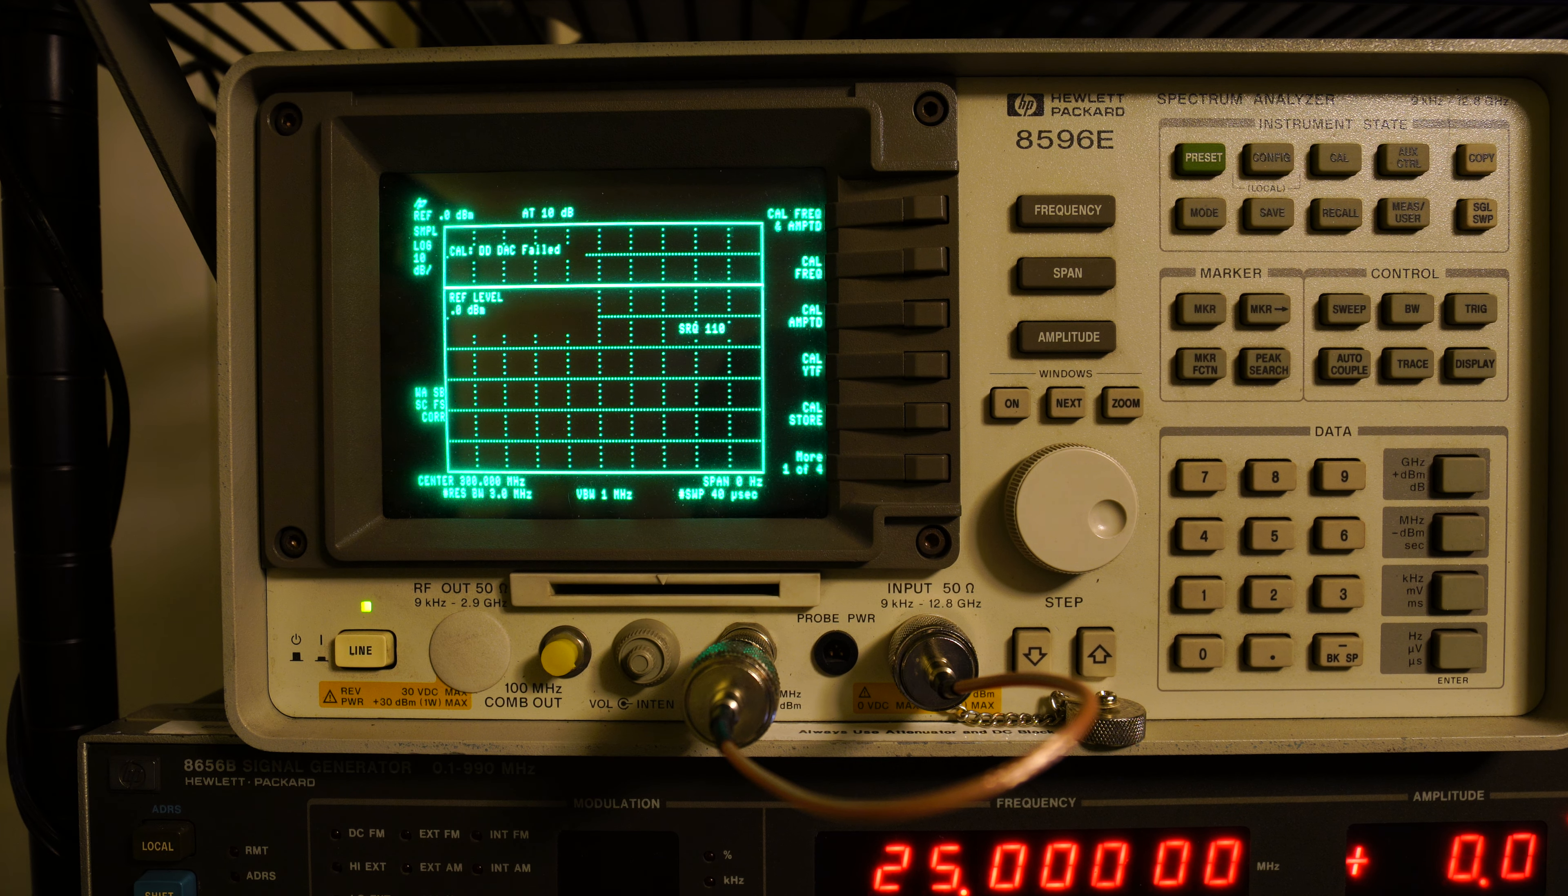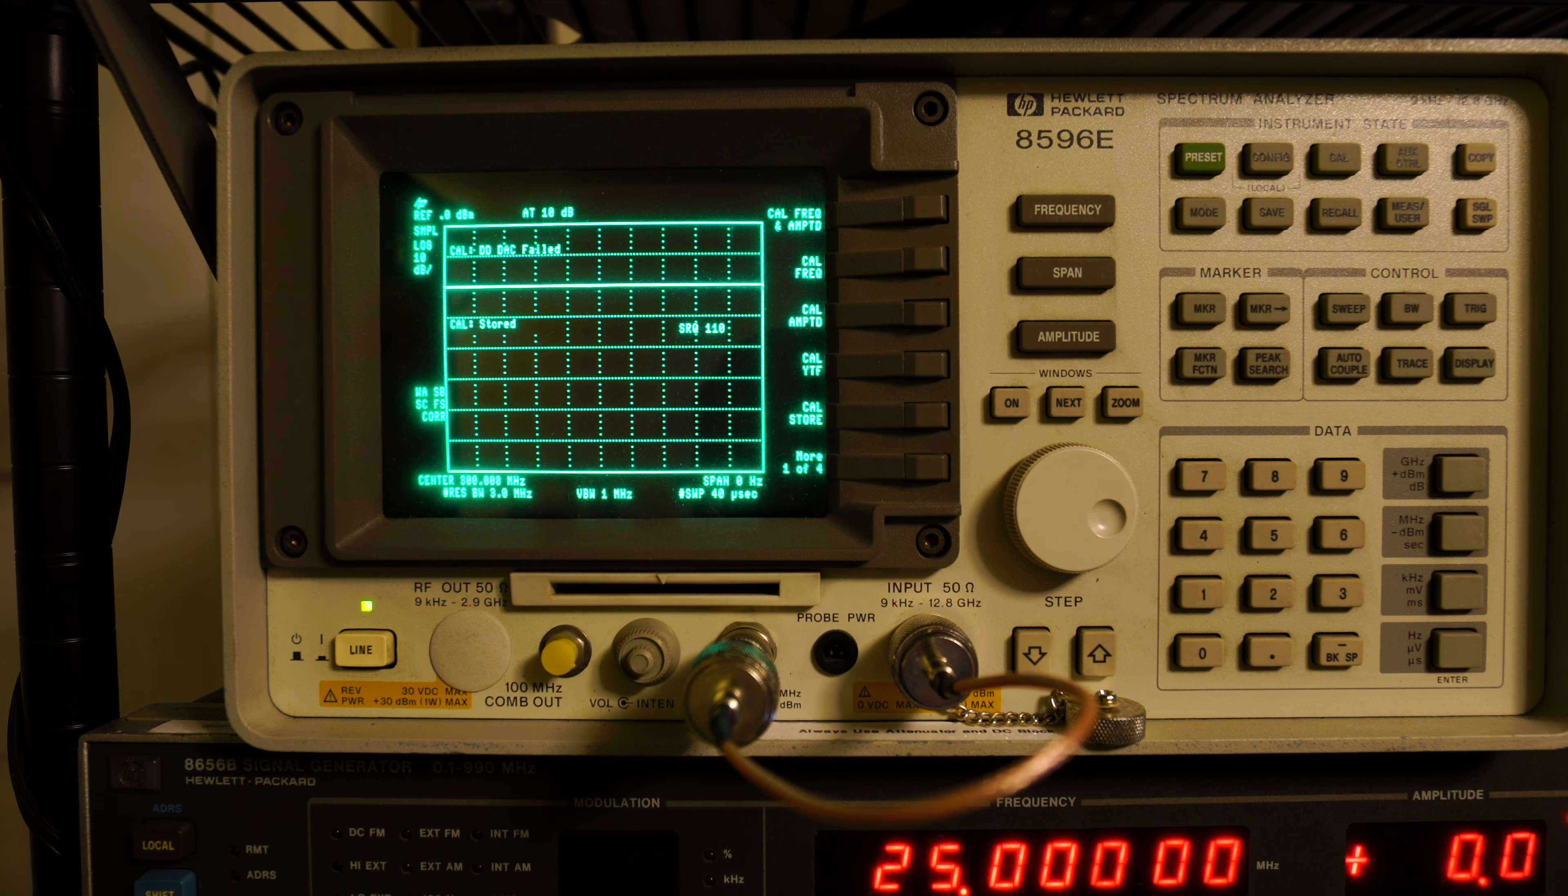All right, there it is. It's finally finished and all you've got to do right here - it says Cal Store. See that? I hope you can read that. Press that and it says Cal Stored. It's through, it works. And then if I press Reset, it'll come back with just that display of the output of the calibrator.